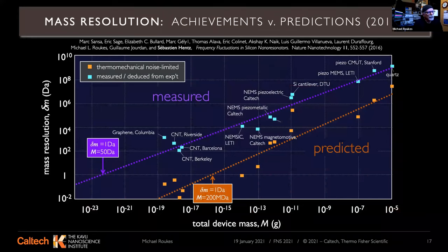If you use thermomechanical noise to predict the mass sensitivity, this is a plot from a paper organized by Sebastian Hentz and published in collaboration with us in 2016. Using thermomechanical noise, what we find is that for the whole range of resonators measured as of 2016—this is a bit of an apples and oranges comparison—the measurement is essentially 3 to 4 orders of magnitude worse. This has plagued us for the longest time and limited us to mass sensitivity, for larger devices that can accommodate proteins, in the range of 10 kilodaltons and up.